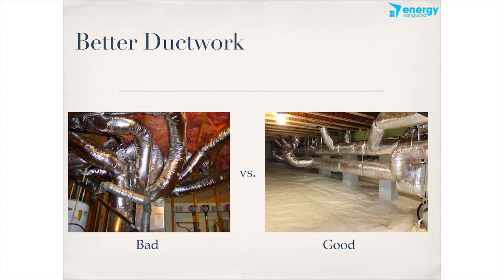This is an Energy Star house in Nashville. I just saw this in the summer. A beautiful duct system. And since it's Energy Star, it has to be commissioned so that the airflow in the different rooms has to be measured and make sure that they get the right amounts. We know how to do this. It's not that hard. Yes, it takes a little bit longer to do it right, but I would rather have a minimum efficiency air conditioner and heating system with a really good duct system than a super high efficiency heating and cooling system with a really bad duct system.